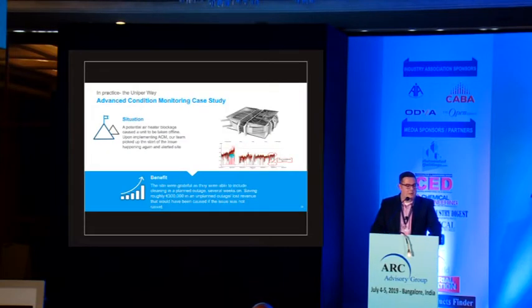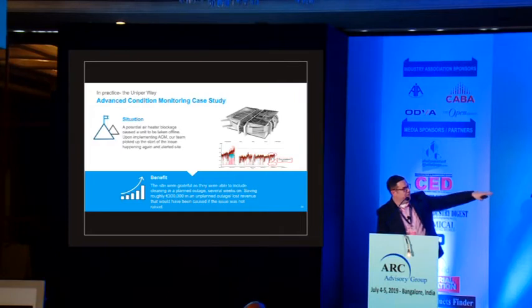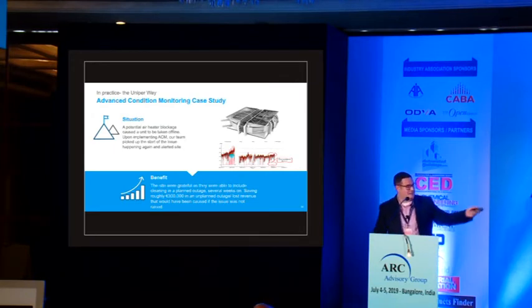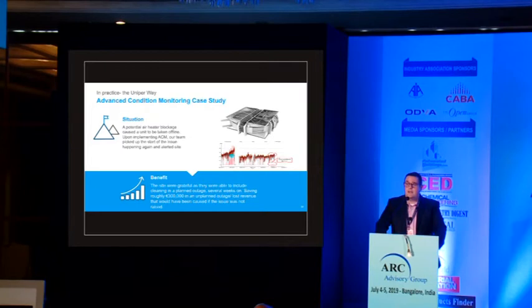Another issue was a potential air heater blockage. You can see on the left of the diagram where the issue had caused the unit to trip, and we'd started monitoring just after that trip. You can start to see the issue beginning to happen again where it says consistent error. That was within the DCS alert limits, so it was just a note our condition monitoring team made to the site to say you might want to see this because it's going to happen again.